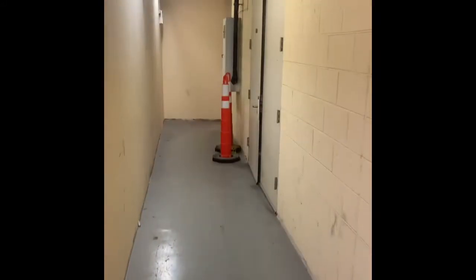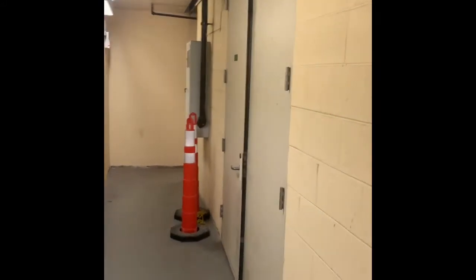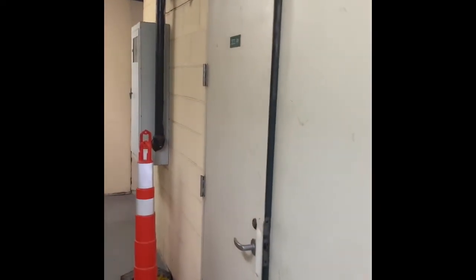All right, we're gonna go and head downstairs, start at the ComEd vault, and we will start our field trip of building power distribution. All right, we're gonna start off by going inside a ComEd vault. This is not the main vault. Typically, you would never ever be allowed inside a ComEd vault without a representative from ComEd being with us. However, as you can see, the door is ajar. It has been broken for quite some time, which enables us to go inside and take a look around.